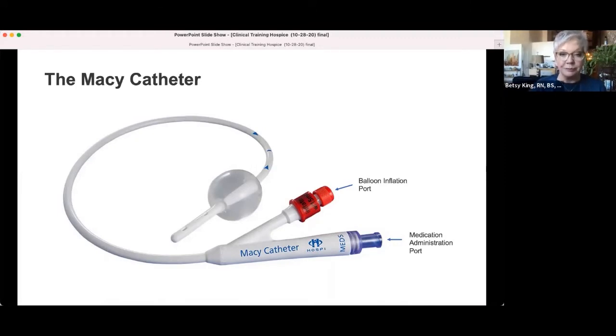Well, down on the shaft of the catheter, you'll find some placement marker lines. Those are there to assist you in knowing how far to insert the catheter before you inflate the balloon. There are two blue triangles or arrows with a blue line right in between them. Simply insert the catheter until this blue line is right outside the patient's body, and then you're in the proper place to go ahead and inflate the balloon. It will be up above the rectal sphincter. And again, there are the 4 holes at the tip of the catheter where your medicine comes out and is dispersed into the rectal wall.